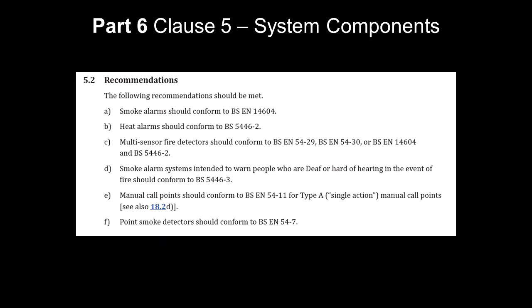And what we're looking at is smoke alarms should conform to BS EN 14604. Now, that's your typical domestic smoke alarm. So commercial premises, and the whole standard of Part 1, does not allow the use of domestic smoke detectors. I see it quite often, and years ago, when I used to do a lot of shop fitting in petrol stations, for example, it was a requirement to install just a main smoke detector, whatever it was, in the shop, and that was it. And obviously that's a commercial premises.